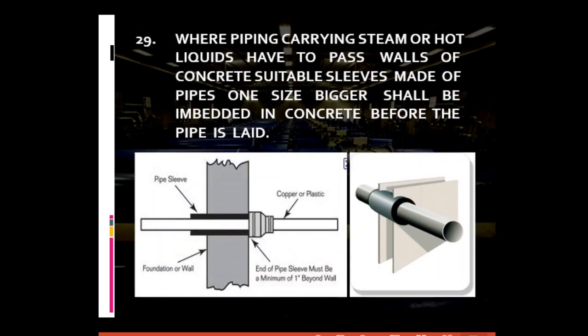For general piping requirement number twenty-nine: where piping carrying steam or hot liquids has to pass through concrete walls, suitable sleeves made up of pipes one size bigger should be embedded in the concrete before the pipe is laid. If pipes conveying substances of varying temperatures are required to pass through concrete walls, they should be provided with sleeves to allow thermal movement of such metallic pipes, preventing any structural damage to the walls and avoiding the buildup of thermal stress.